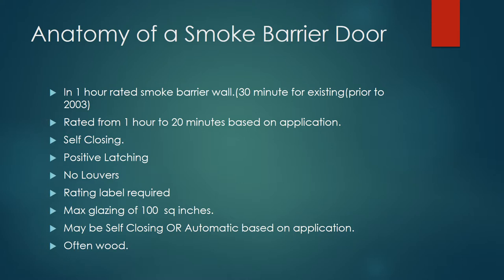Now let's talk about the anatomy of a smoke barrier door. Smoke barrier doors are typically in a 1-hour rated smoke barrier wall, or 30-minute for existing construction prior to 2003. They are rated from 1-hour to 20 minutes based on application, and require self-closing with positive latching. An important distinction from fire doors: no louvers are allowed in a smoke barrier door. In a purely fire door, louvers can be used if they're fusible-linked or contain intumescent material that will close during a fire.